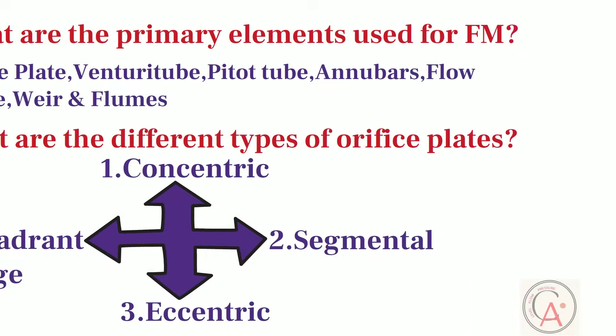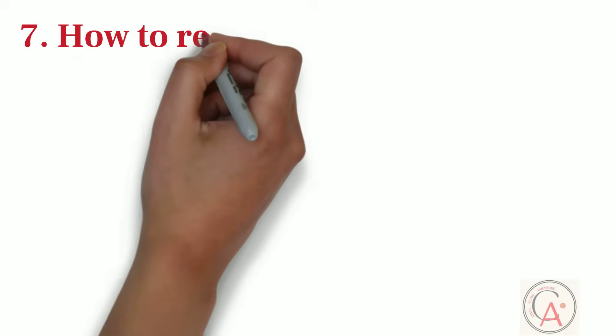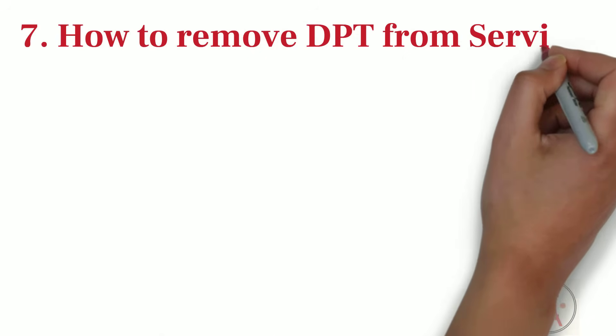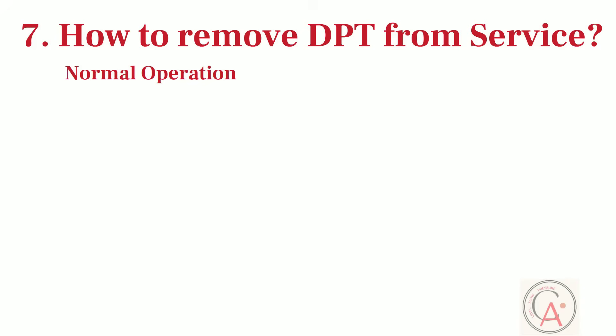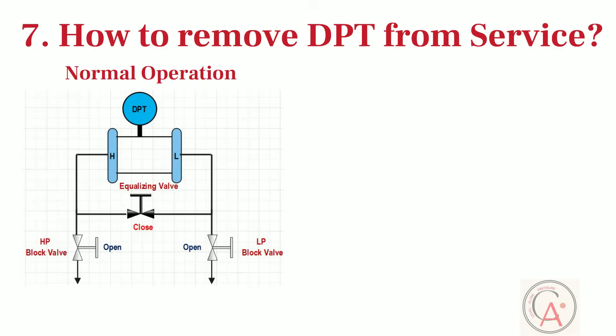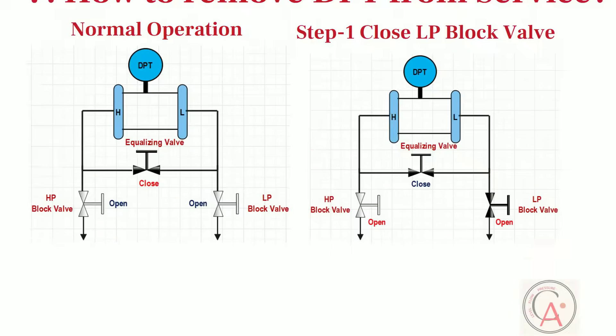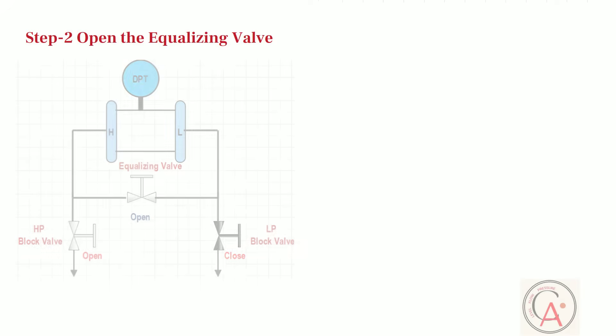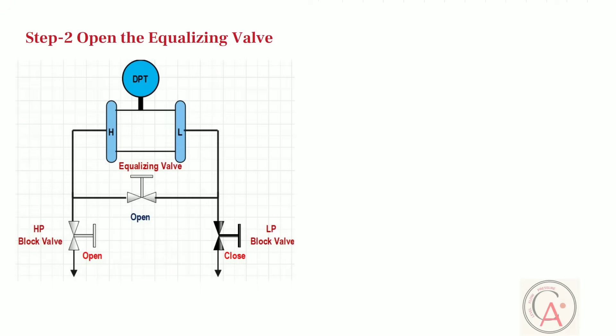Seventh and most important type of technical interview question is, how to remove differential pressure transmitter from service. In normal operation, both high side and low side manifold valve is in open condition, and equalizing valve is in close condition. To remove DPT from service, close the low pressure side block valve. Then open the equalizing valve. At the end, close the high pressure side block valve.